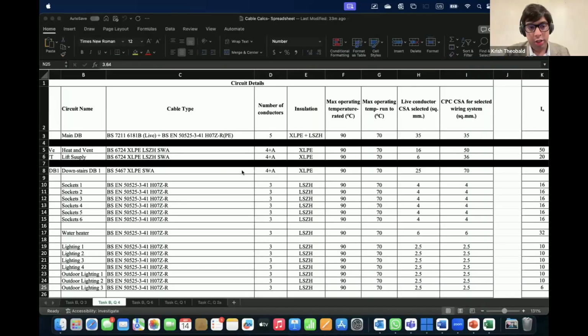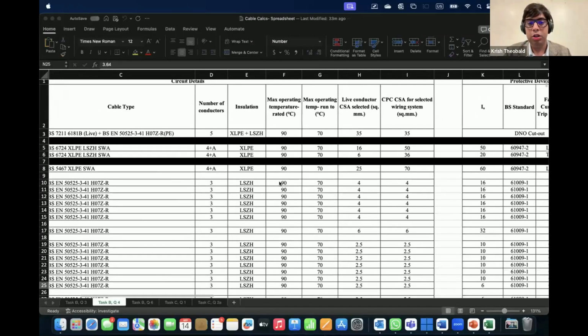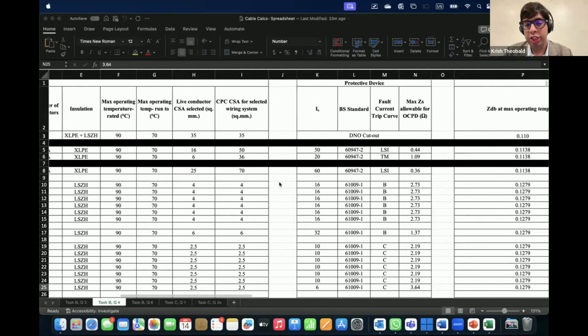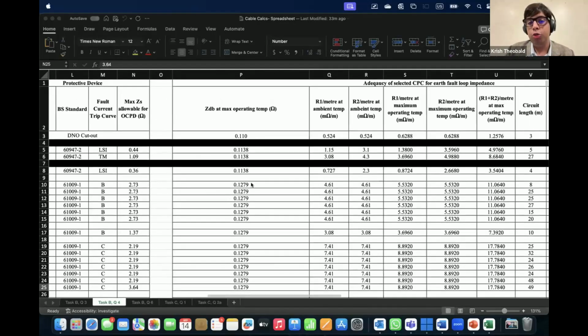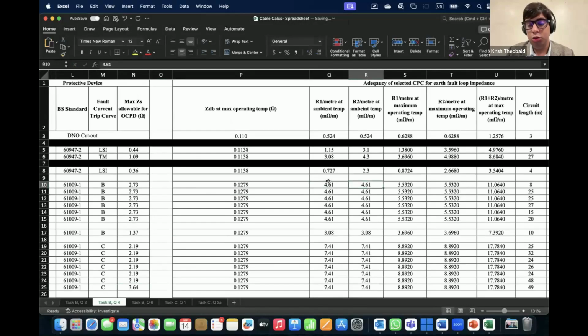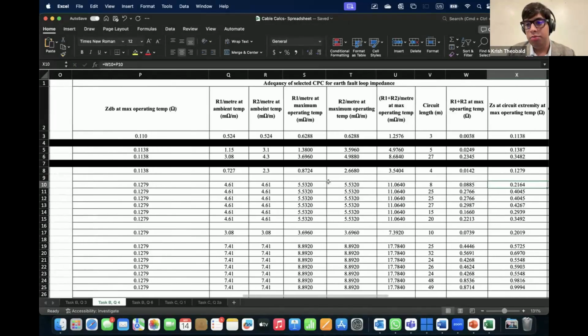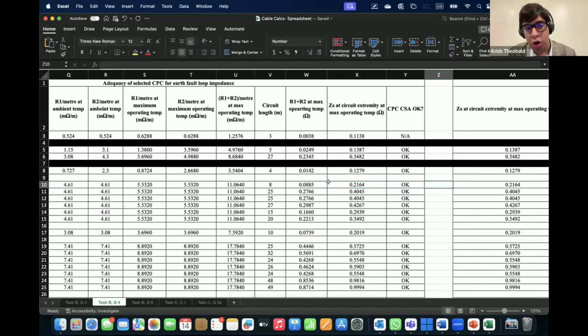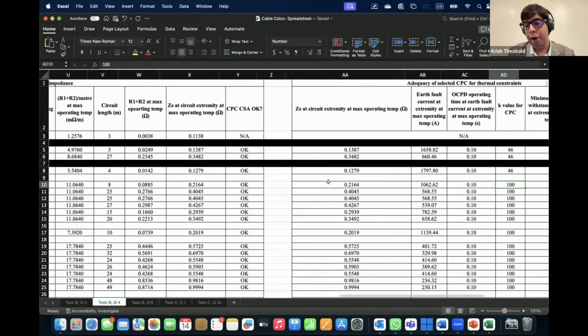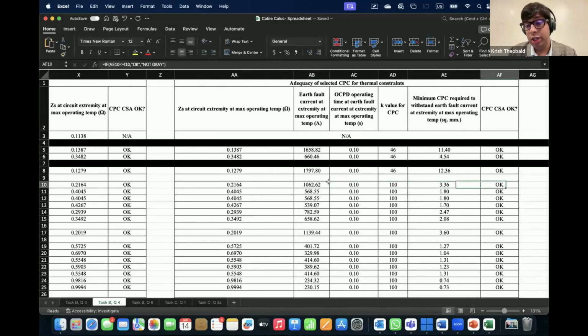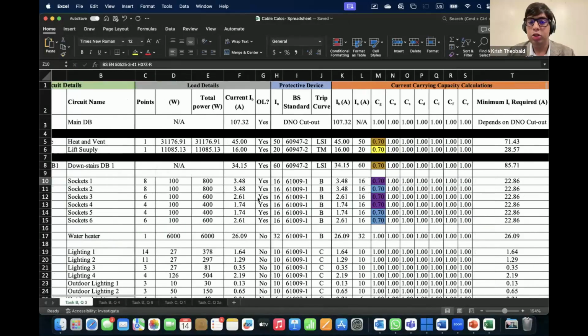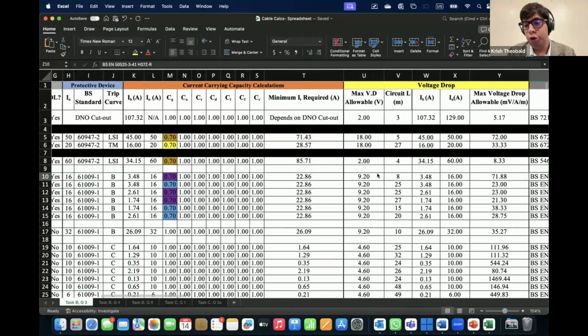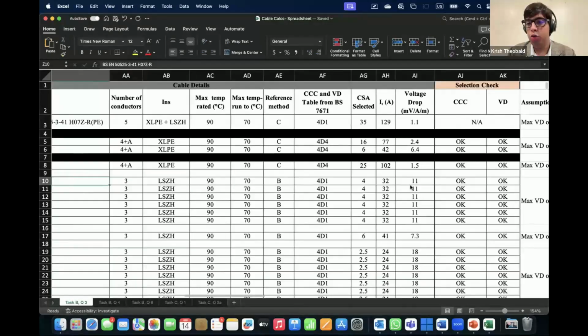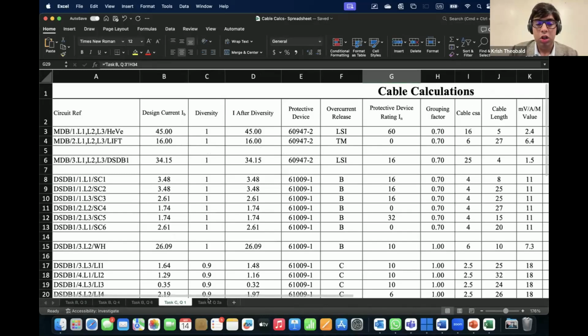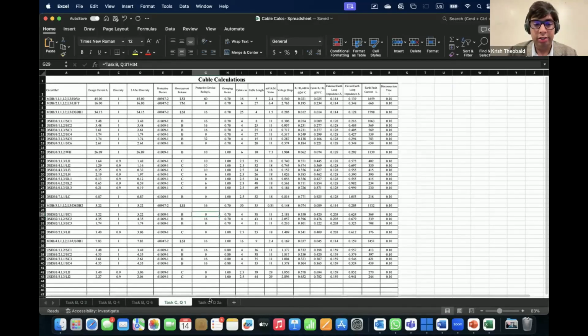Right. So we've got cable type. What is the cable? What is the maximum operating temperature? What are we running it to? Cross-sectional areas. What is the protected device? Then, what is the earth fault loop impedance? What is the resistivity of the cable? So then what is the earth fault loop impedance going to be? Is it okay or not? Then is the protective conductor selected? Can it withstand the fault current? The electrical energy let through by the protective device, is it okay or not? You've got your current carrying capacity, obviously, so all your rating factors. What is the voltage drop? Again, what are we running it to, and is it okay or not? So maximum demand and diversity is also there. A lot of things are there, really.